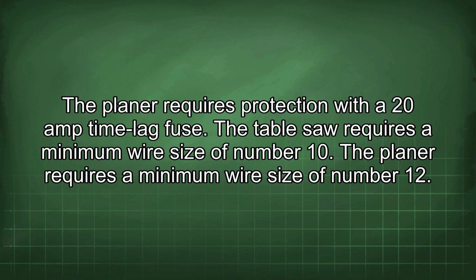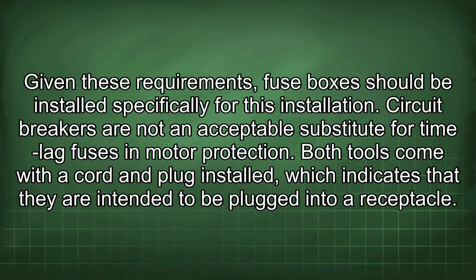The table saw requires a minimum wire size of number 10. The planer requires a minimum wire size of number 12. Given these requirements, fuse boxes should be installed specifically for this installation. Circuit breakers are not an acceptable substitute for time lag fuses in motor protection.